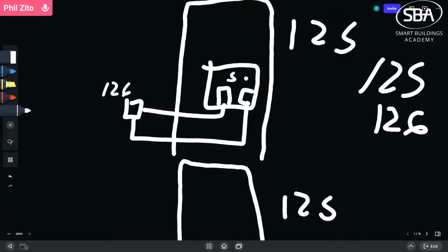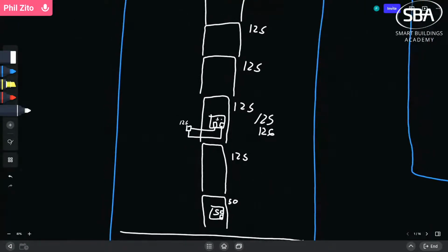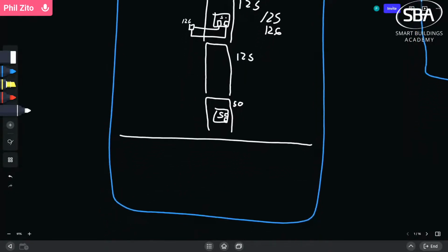But this would be on each floor. And then we would have to have one of these devices having a BBMD BDT capability to interchange between these. Now we would have a port, and all of these switch ports on each floor would most likely go back to a router, and this router would have routes to each IP address on each floor.